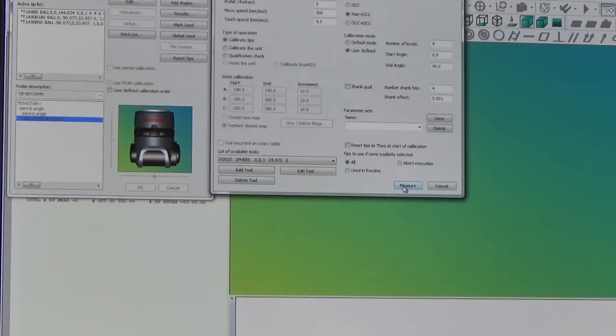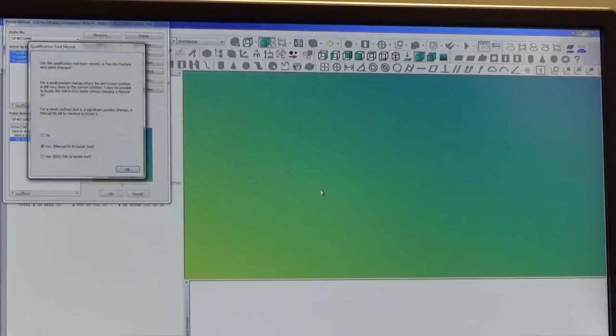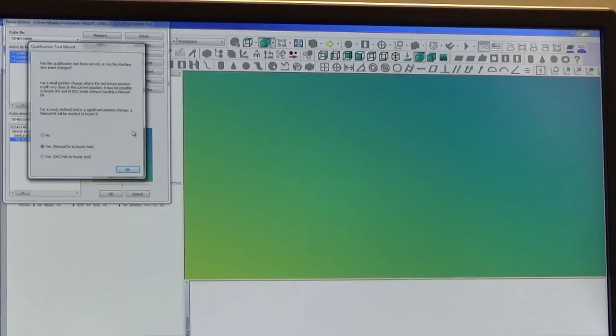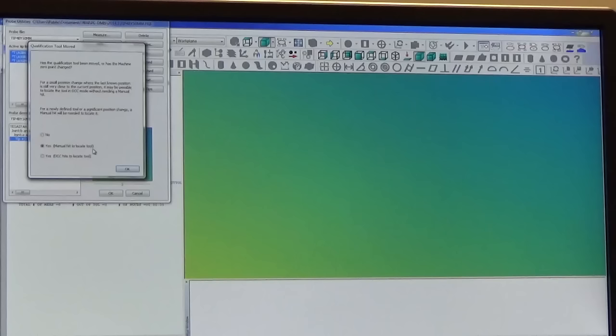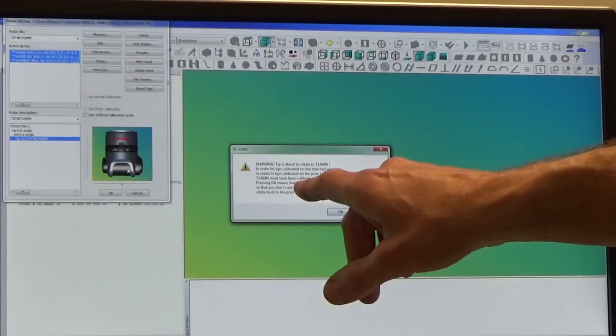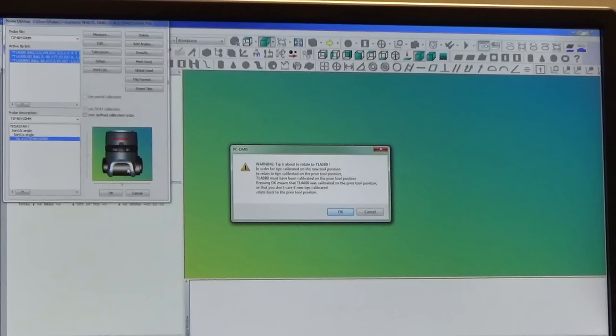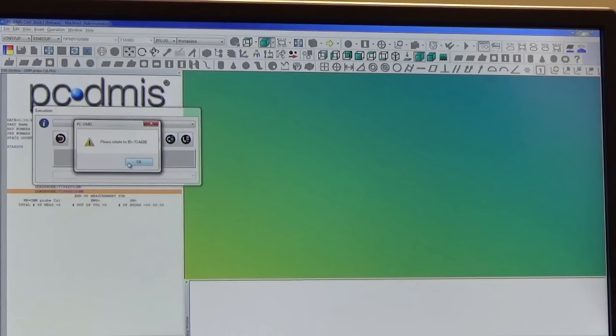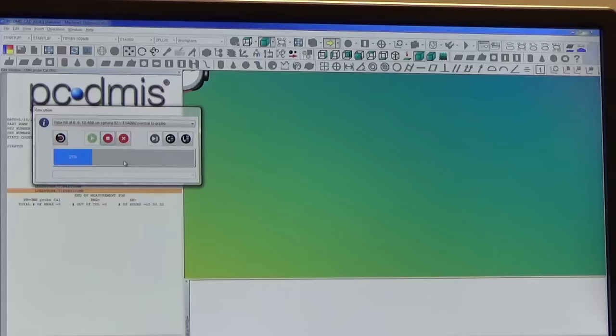Down here at the very bottom is a listing of the sphere. So we're ready now, we're going to say measure. And now it's asking us has the qualification tool been moved, we're going to say yes it has. A manual hit will locate the tool, it's a safe bet whenever you put the sphere on the table. Now it's telling us here to make sure that we have the tip rotated to zero and zero which means that the probe is straight up and down. Now it's asking me to take a hit on the top of the sphere.